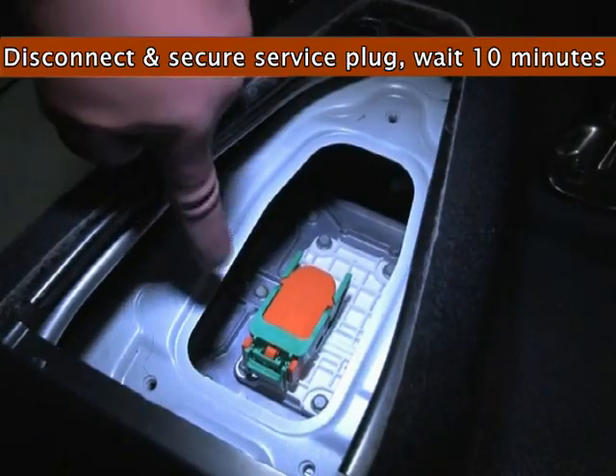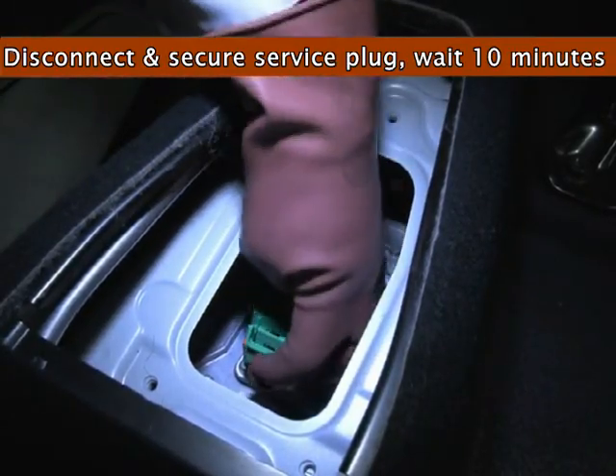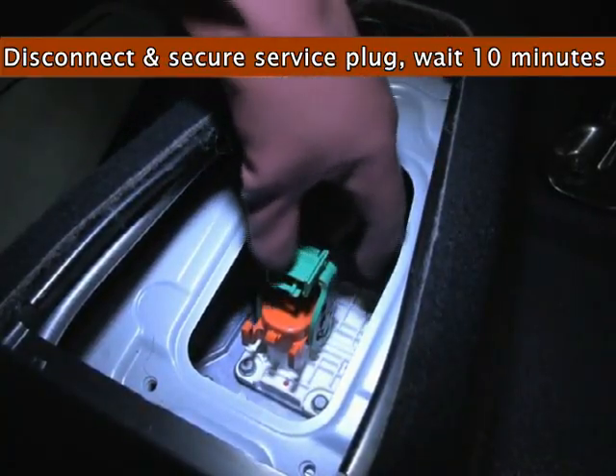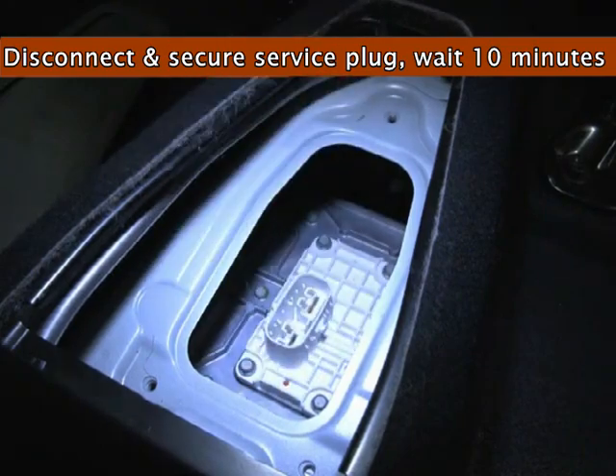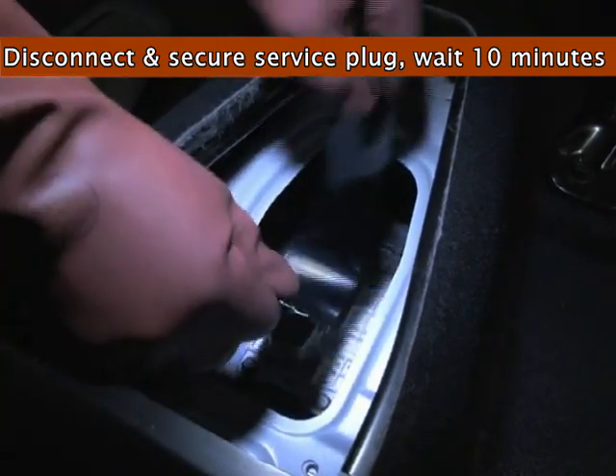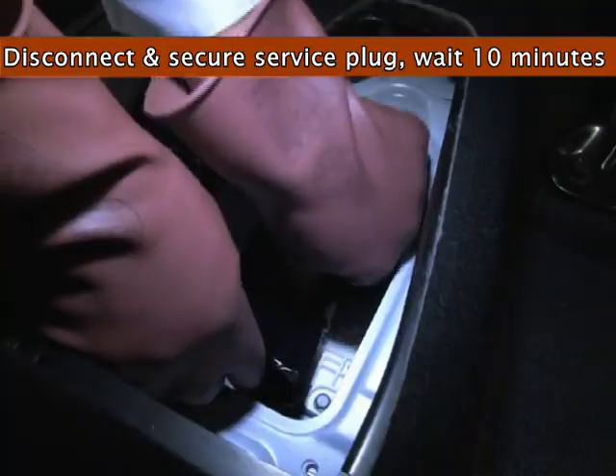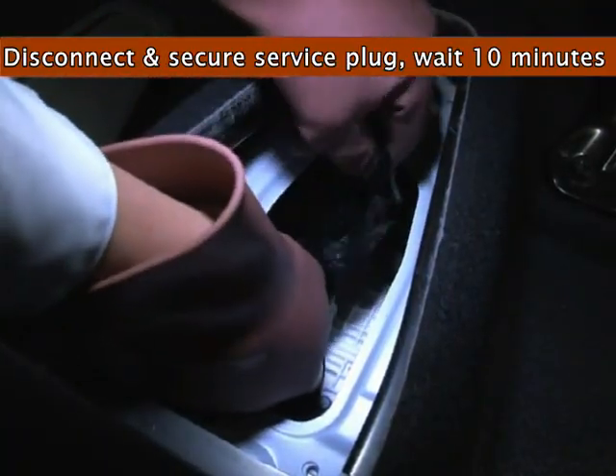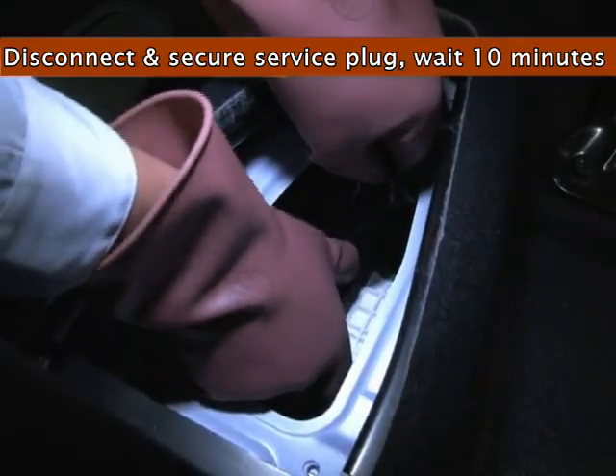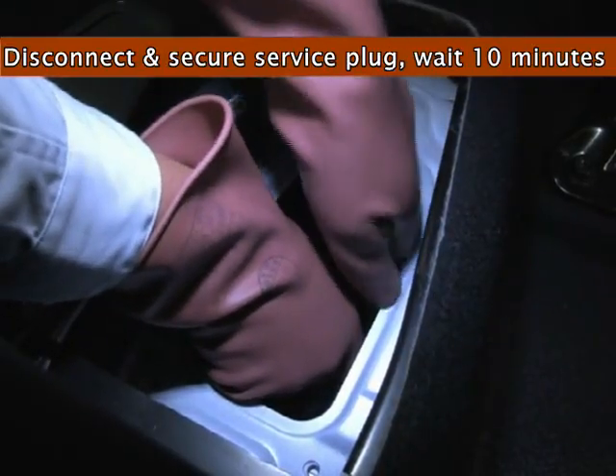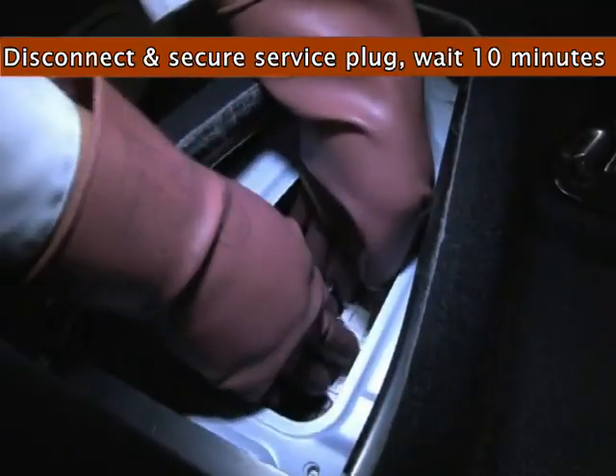Remove the service plug by first releasing the lock tab and moving the lever upward. Push the secondary latch on the lock lever and rotate the lock lever fully upright to disengage the service plug. Secure the service plug and cover the service plug connector with insulating tape. Wait 10 minutes for all potential voltage to equalize.